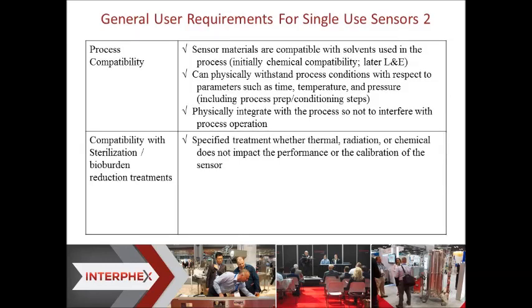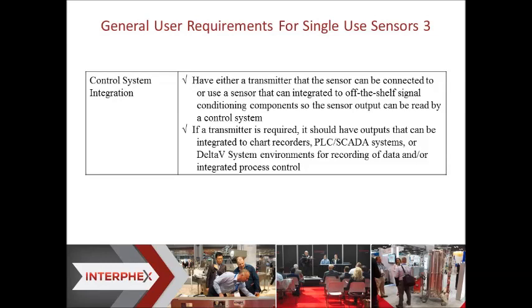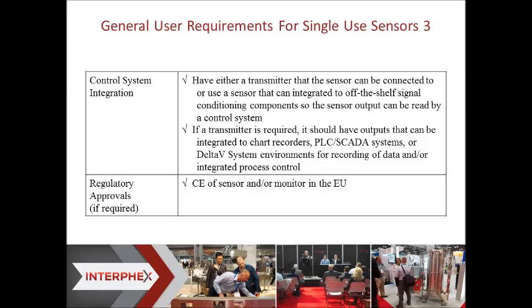In this next area is where a lot of sensing technology has failed. Gamma irradiation and other treatments can be very detrimental, and can impact certain materials, and can also impact calibration. As far as control system integration, the user would need to decide whether they just want a local display, or whether they want the reading transmitted to a higher level control system and potentially a historian. Particularly in Europe, there are more regulatory requirements such as CE and others, but that would need to be decided up front. You don't want to get towards an implementation and find out that something you require doesn't exist.